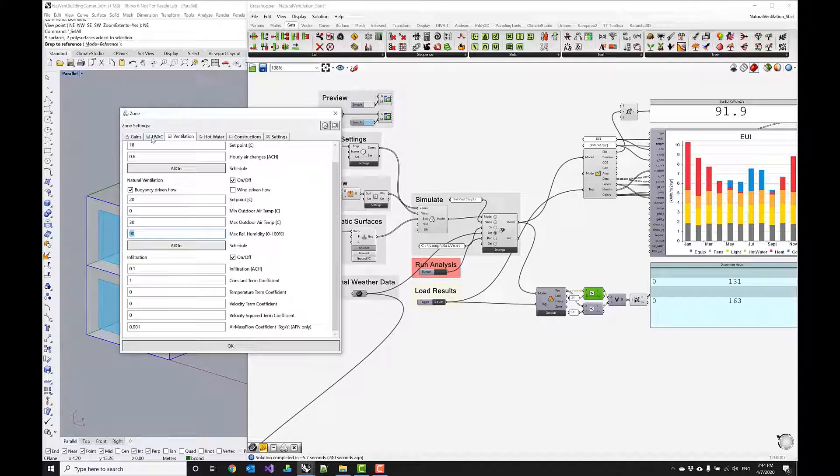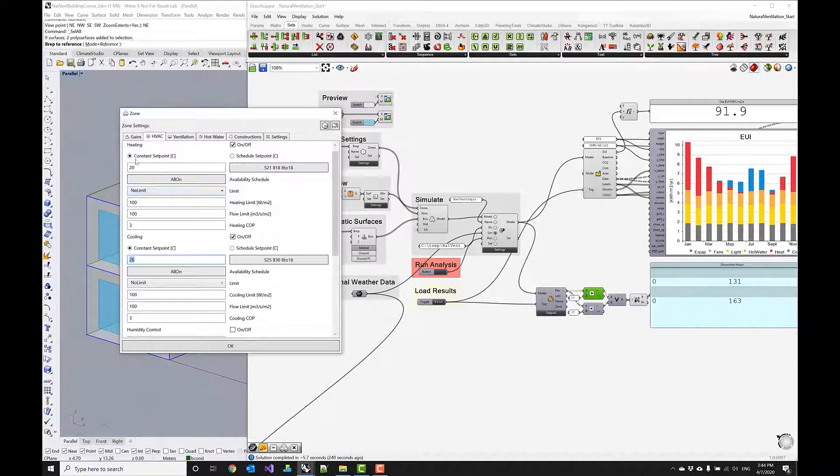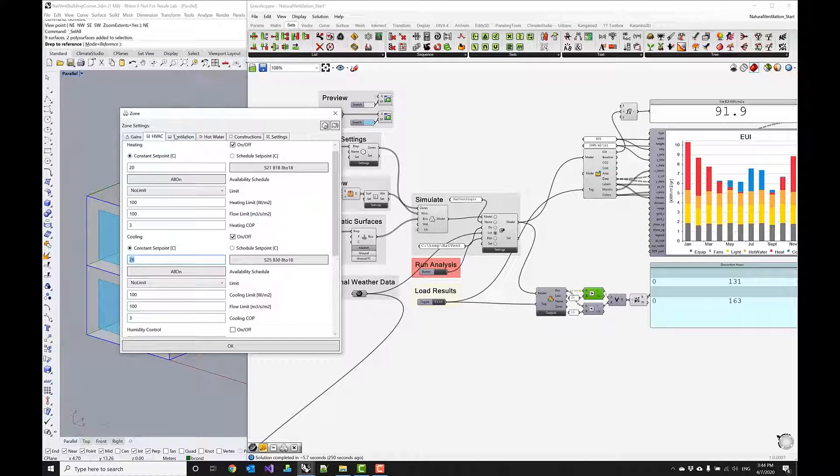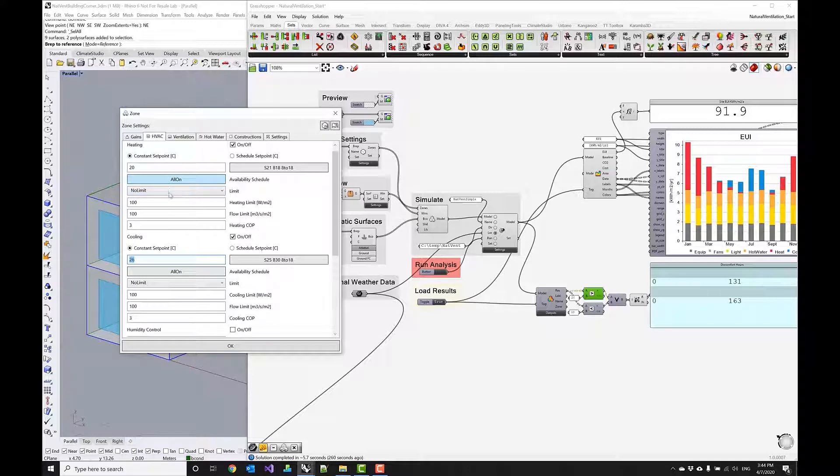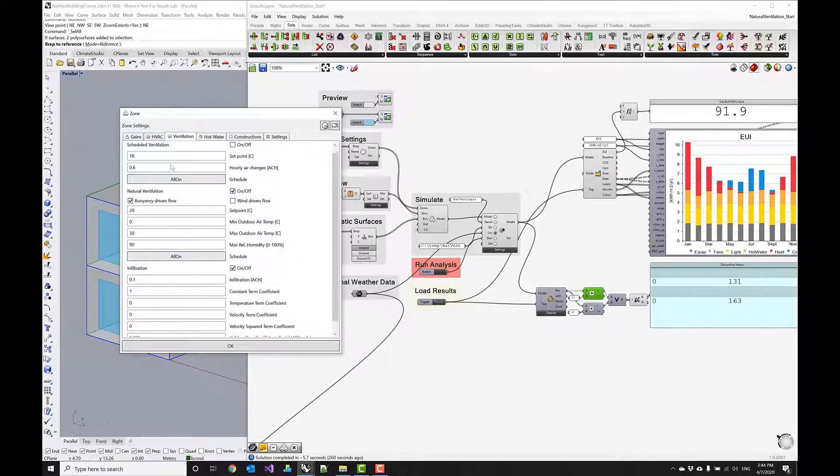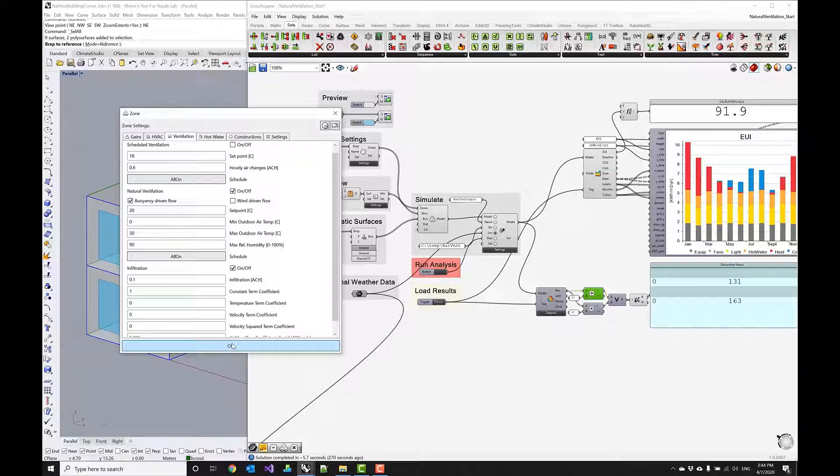Remember this building was set up with a full HVAC system with heating and cooling and taking a look at these set points actually what we can see here is that these systems now we have three - the natural ventilation, the heating and the cooling system - they can start fighting each other so now we have to make sure that the heating system and the cooling systems cannot be turned on when this building is trying to naturally ventilate and for that we have to develop a control strategy and this is kind of the hardest part about the natural ventilation setup.